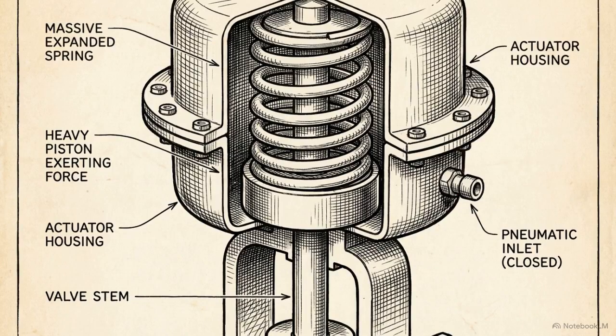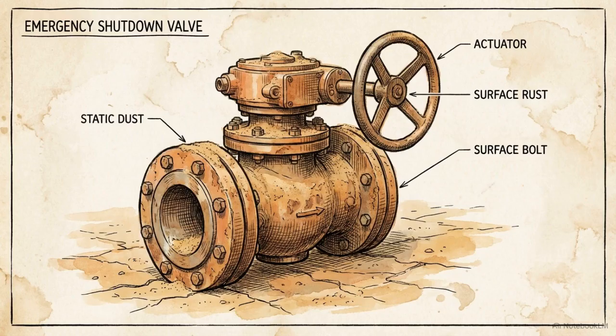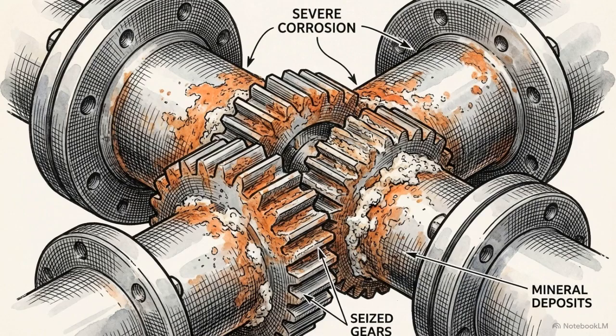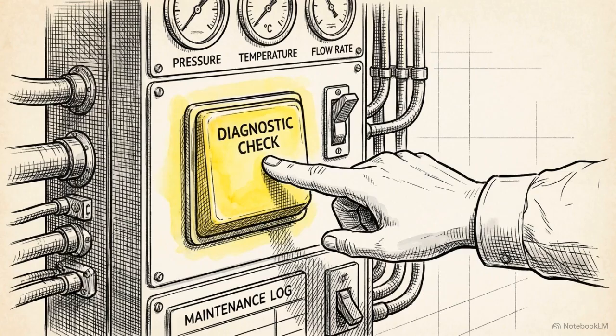They utilize heavy spring return actuators that mechanically force the valve shut the moment electrical power is lost. These safety valves sit fully open for years at a time. The primary risk is stiction, corrosion or mineral deposits causing the mechanical parts to seize together precisely when the plant needs them to close. To prevent stiction without halting production, engineers use partial stroke testing. The PLC commands the actuator to engage, closing the valve roughly 10% of its travel distance to prove it moves freely, before returning it to the fully open position.